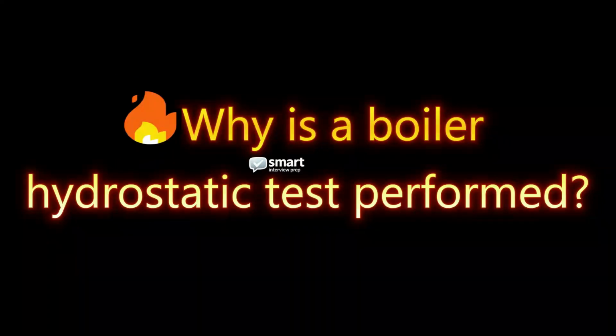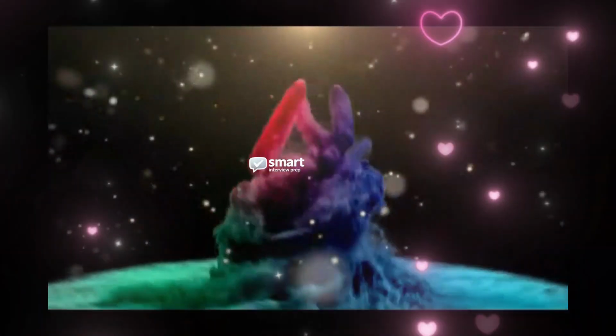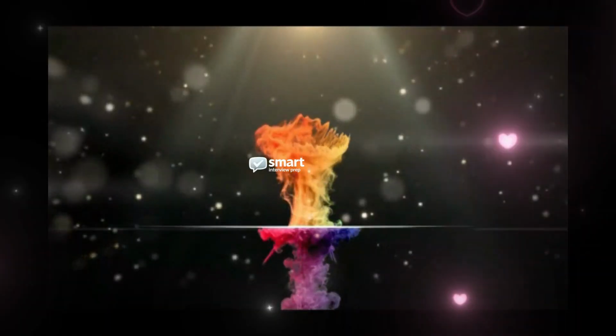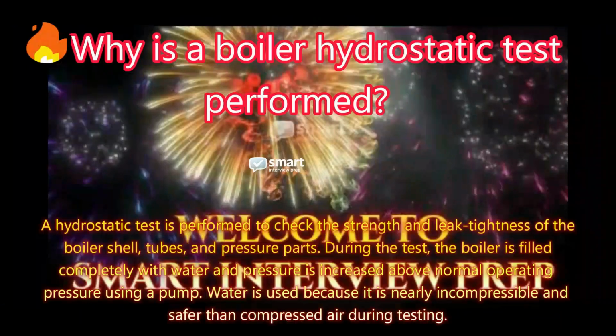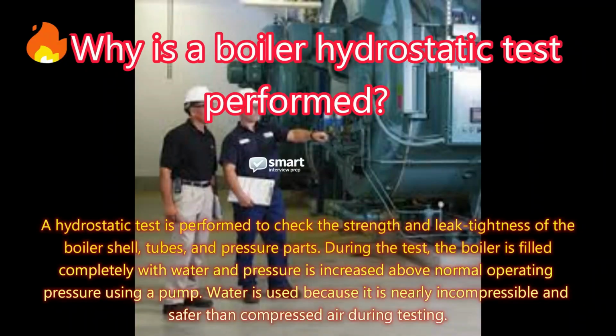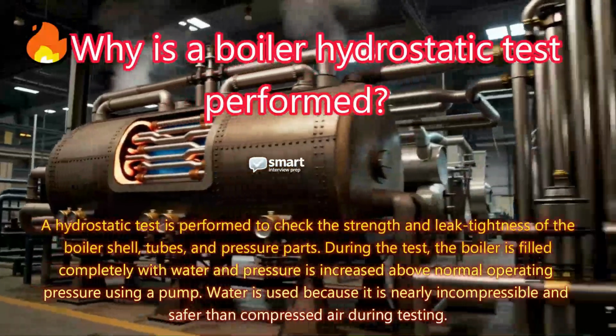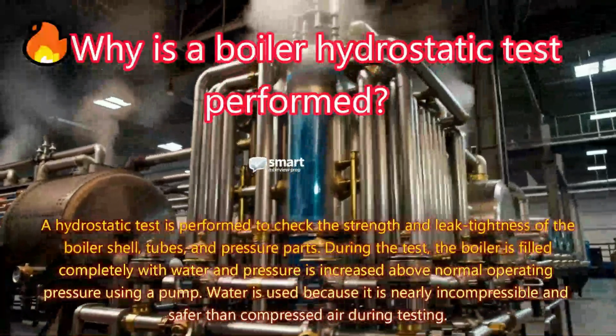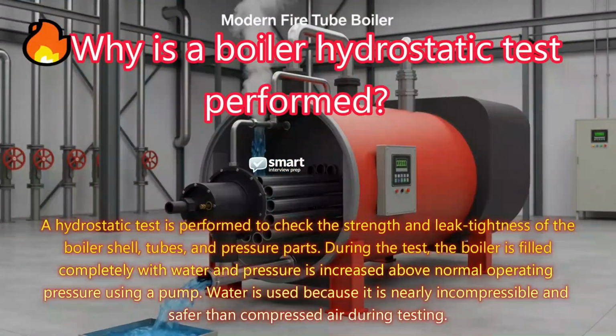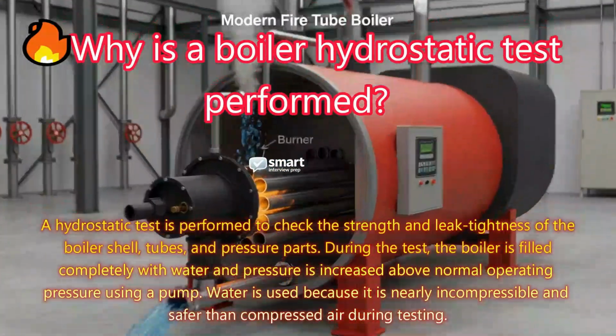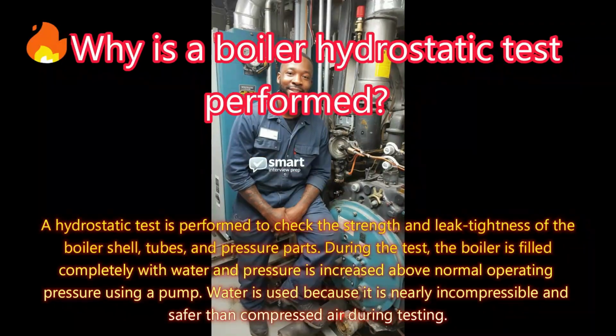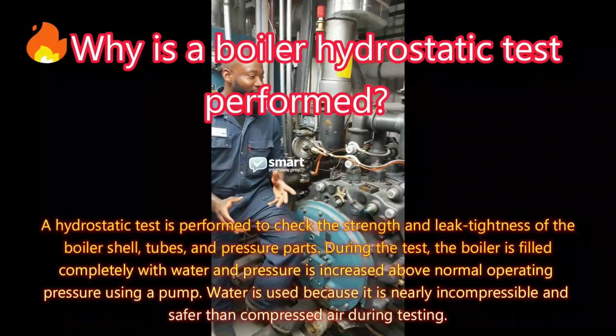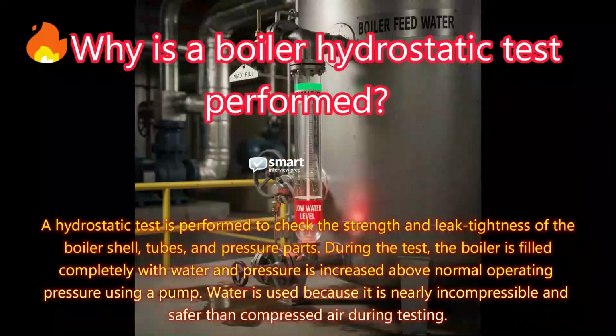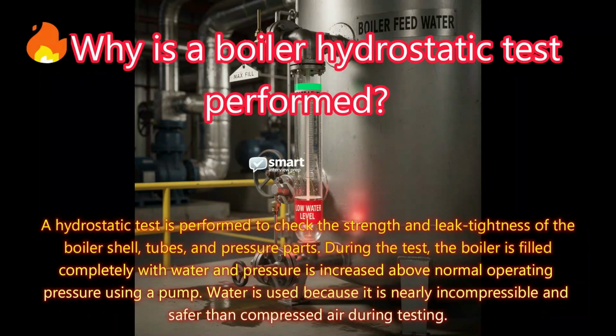Why is a boiler hydrostatic test performed? Answer: a hydrostatic test is performed to check the strength and leak tightness of the boiler shell, tubes, and pressure parts. During the test, the boiler is filled completely with water and pressure is increased above normal operating pressure using a pump. Water is used because it is nearly incompressible and safer than compressed air during testing.